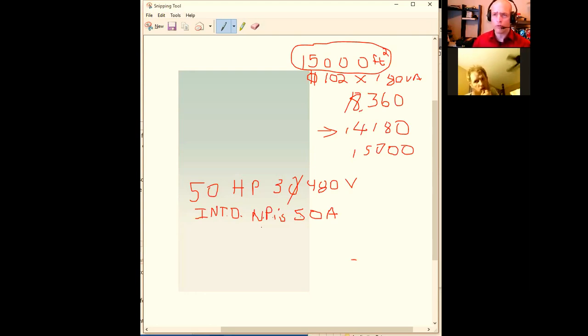just a general everyday motor, those are code required calculations based on the table values in the back almost every time. So what you did, going back there to pick the FLC number for that 50 horsepower, 480 volt motor, is normally what you should do. The nameplate doesn't come into effect except for the heaters, and that's about it. But this is that one weird spot where we've got a specific table for motor wiring on the branch circuit side where you have a non-continuous duty motor. The nameplate's only for the overcurrent, except for a motor that's non-continuous duty.